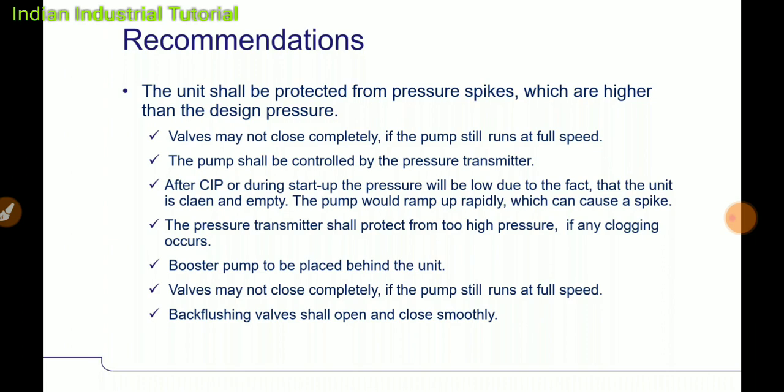If you have these heat exchangers in your plant or a similar system, our recommendation is that these units are to be protected from pressure spikes. Pressure more than design pressure should not go. Valves may not close completely if the pump is running at full speed, and that also we have to take care of. The pump shall be controlled by a pressure transmitter.